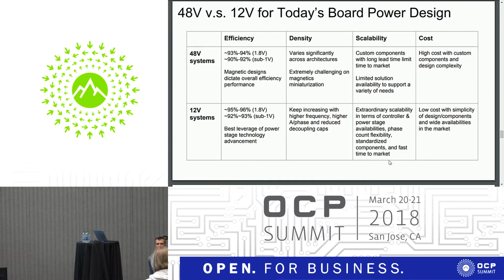I want to back that up and say, by moving the high voltage further out, that allows us to do UPS and distribution at the rack level with 48 volts and lower our distribution losses. We think it's probably like a 1%-ish gain in distribution. Yes, they're all very small.